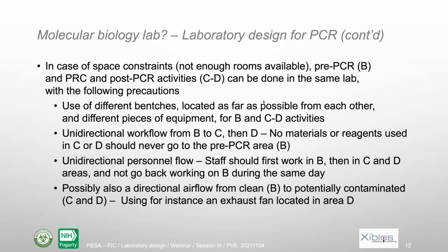And if you use some ventilation system, in that case, you should also use the directional airflow from clean pre-PCR to contaminated C and D, so to PCR and post-PCR. Okay, so even with respect to ventilation, you should use that in order to avoid any contamination of your premix.